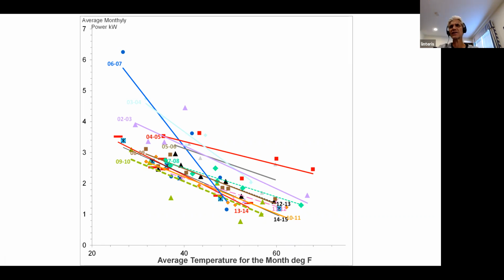The numbers are the years: 2002-2003 is this purple line, when we moved in, and 2014-2015 is the most recent. Generally things moved down over time, though the slope didn't change that much, surprisingly. In fall 2015 we installed the ground source heat pump, which changed the slope by roughly a factor of 2.